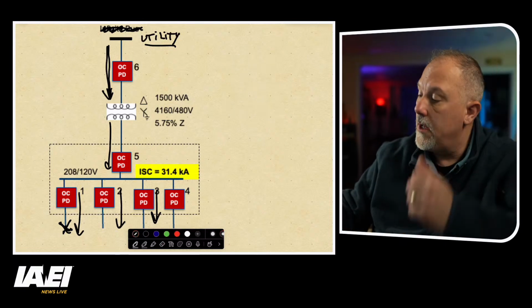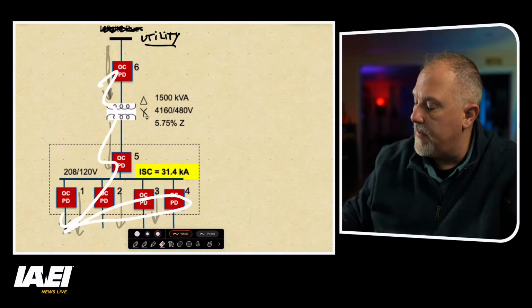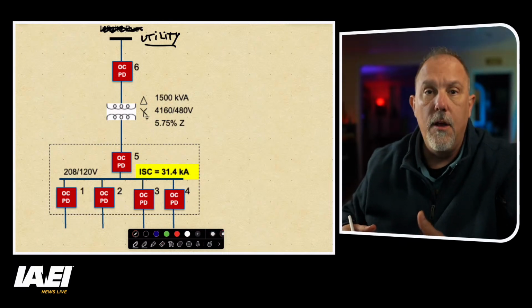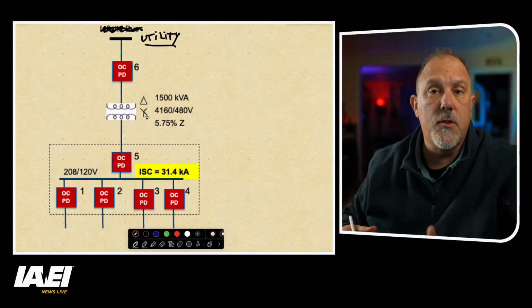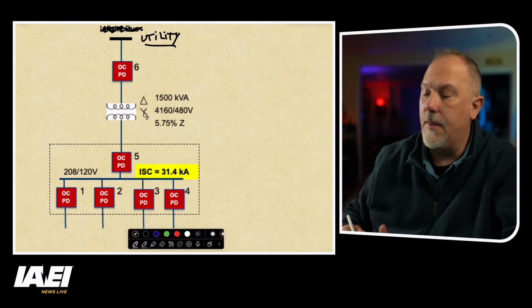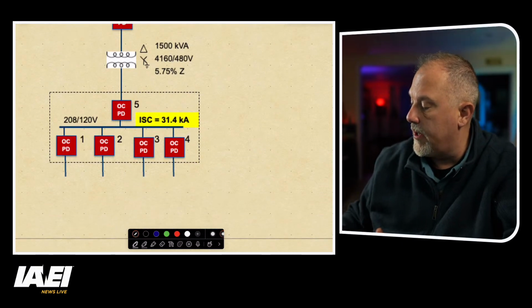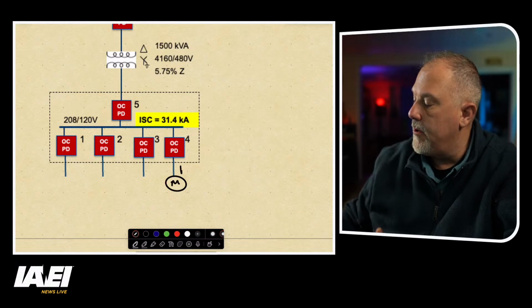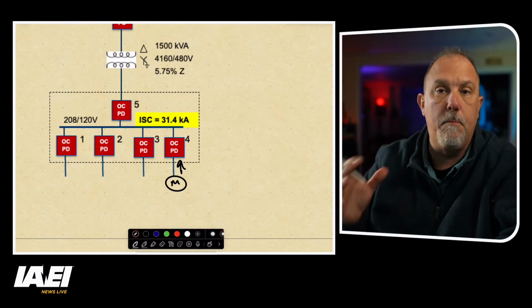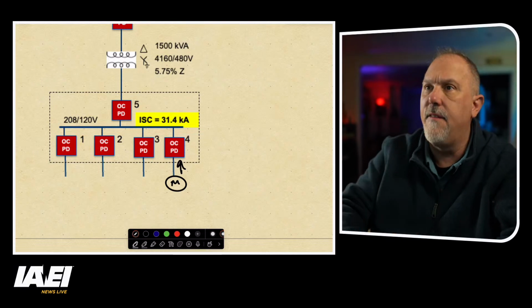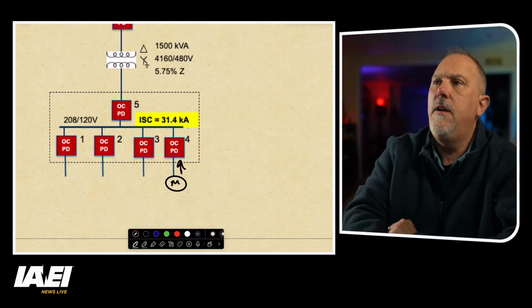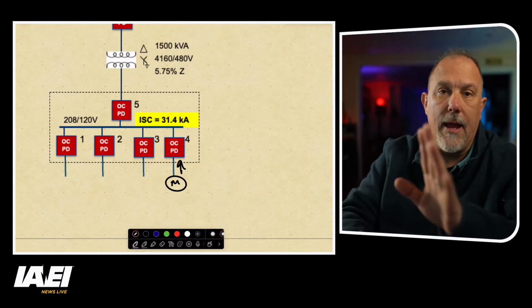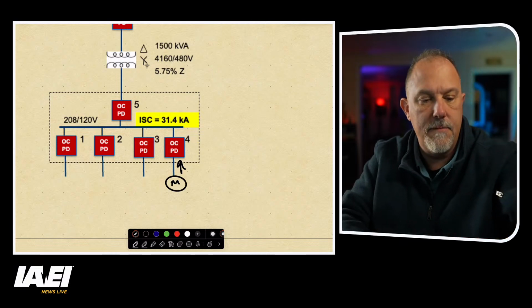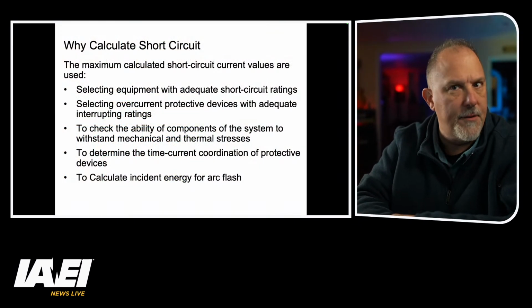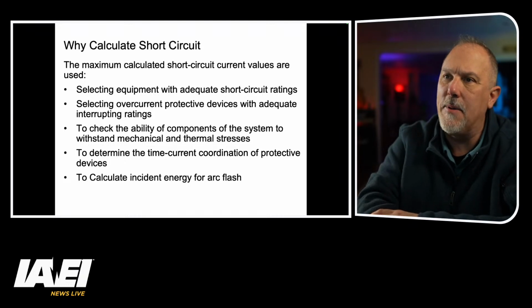So what you have to think about is all of this equipment has to carry and deliver the fault current to where the fault is. And which we did draw earlier, we drew a motor, right? That motor could contribute fault current back to the system. And in fact, here we go. And I know you guys like videos, so life would not be good without a good video. Let's take a look at what happens.